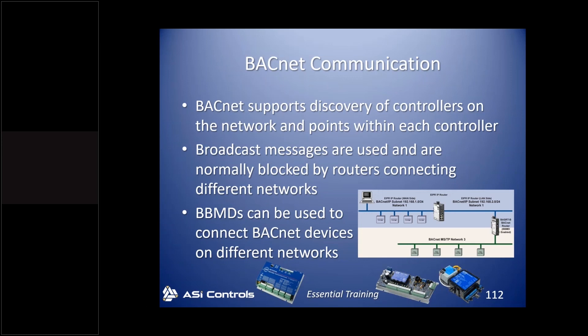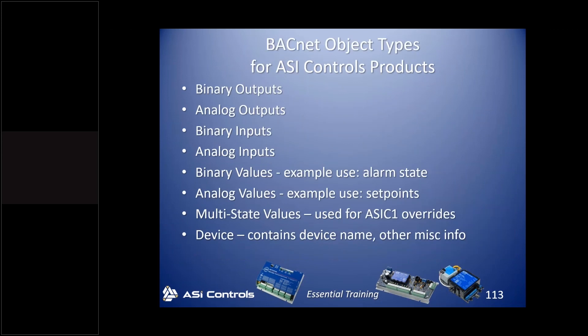A BBMD essentially allows two different BACnet IP networks to be bridged together. They need to know each other's IP addresses so they can communicate. There's actually a BBMD on our network here that's allowing our VPN connection because this is more sophisticated than a typical in-building local network. BACnet also has various objects similar to programmable ASIC/3 controllers — there are objects and instances. Within each object there can be multiple instances, one for each of the binary outputs, analog outputs, binary inputs, and analog inputs — those are the hard I/O points.